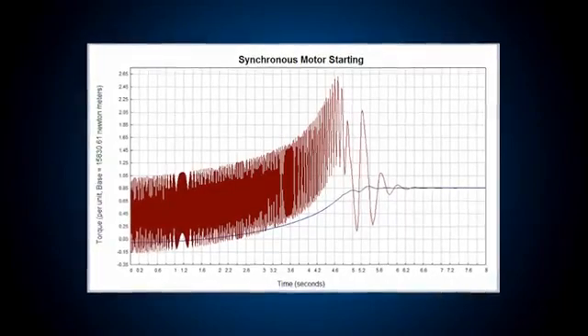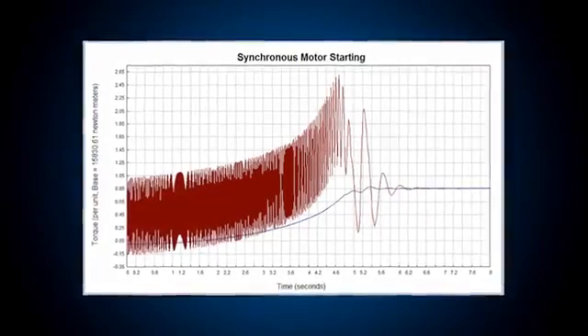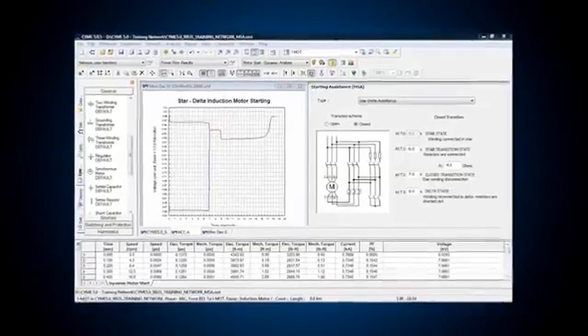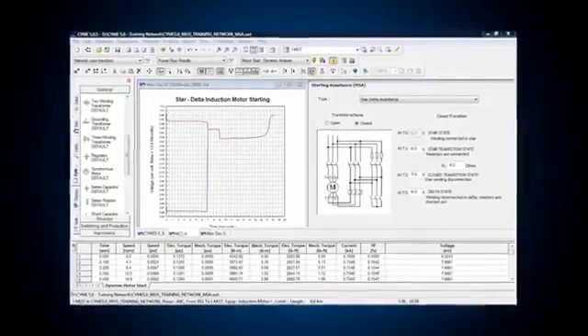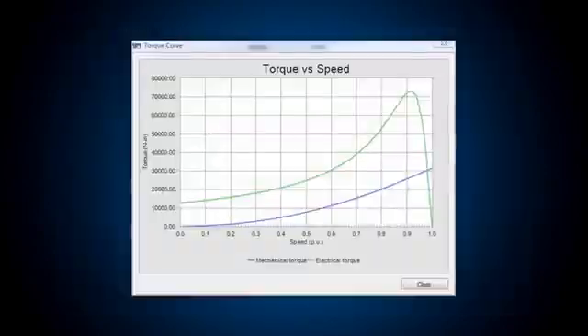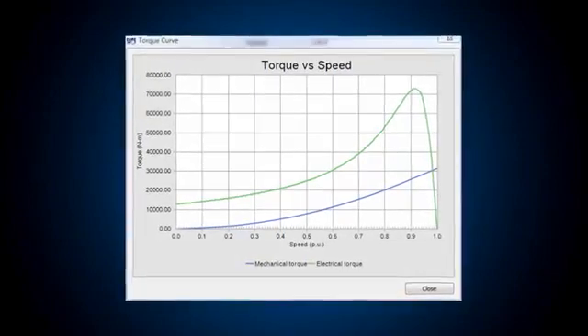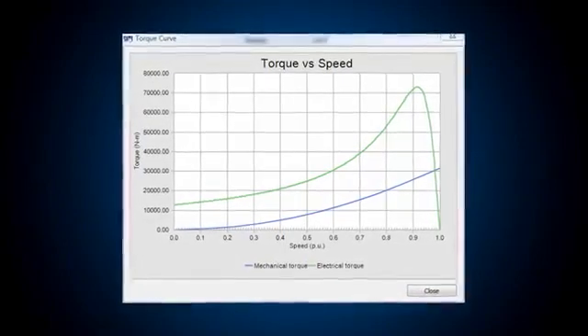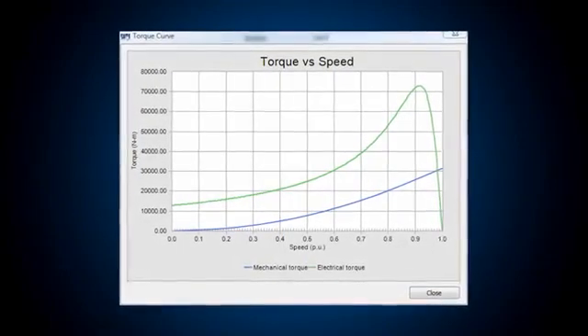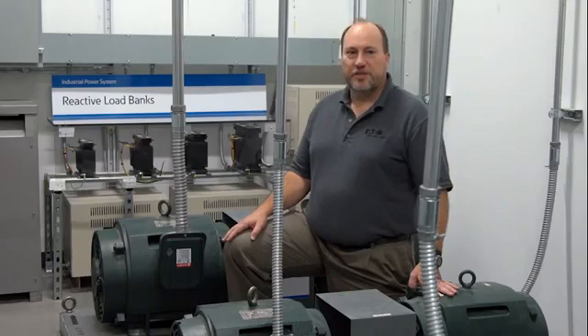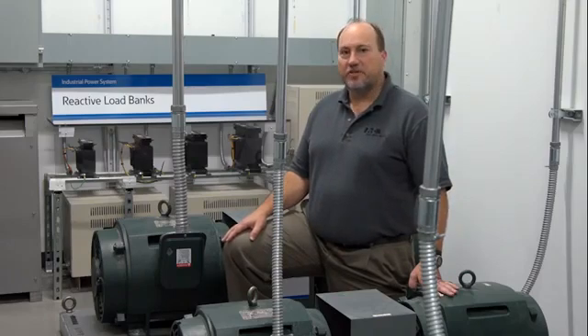Motor starting analysis is much more detailed than a simple voltage drop calculation. System impedances and motor dynamic characteristics such as torque and current at various speeds are considered. With this information, we can calculate the motor acceleration time and all of the associated currents and voltages.